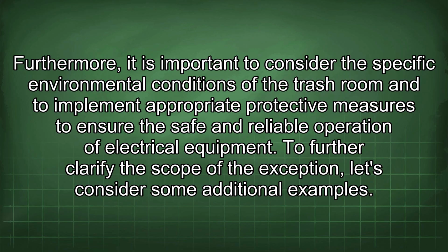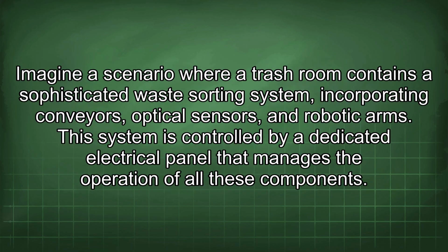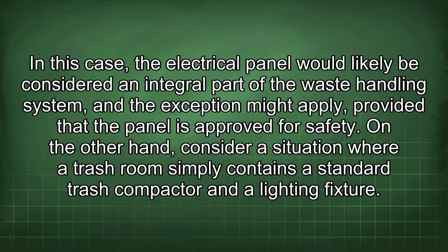To further clarify the scope of the exception, consider a scenario where a trash room contains a sophisticated waste sorting system incorporating conveyors, optical sensors, and robotic arms, controlled by a dedicated electrical panel managing all these components. In this case, the panel would likely be considered an integral part of the waste handling system, and the exception might apply, provided it is approved for safety.